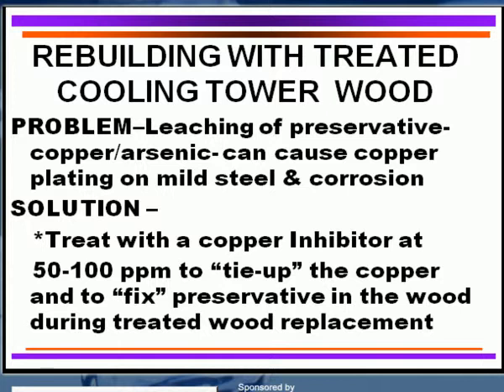but you've got to have enough copper inhibitor to tie up the copper, and we normally look at least 1 ppm of the azole copper inhibitor for every part per million of copper. That's a theoretical amount that you should use. I like to use at least twice as much azole just to make sure you have plenty there, just to be able to tie up that copper so you don't get into serious corrosion problems.